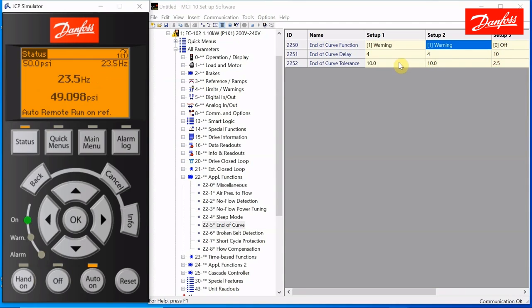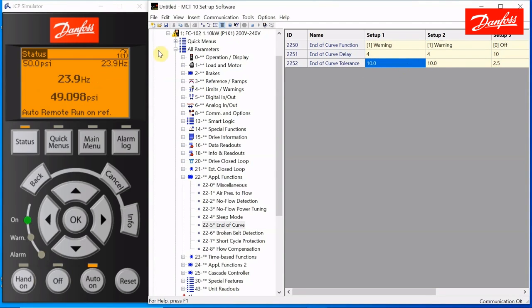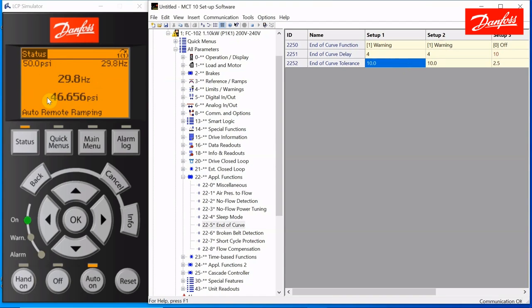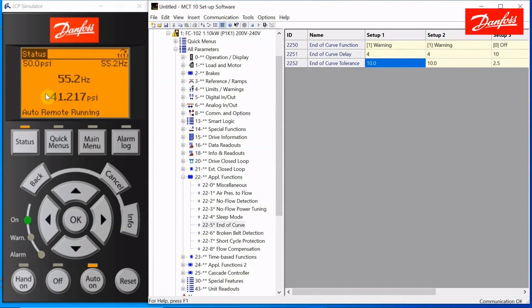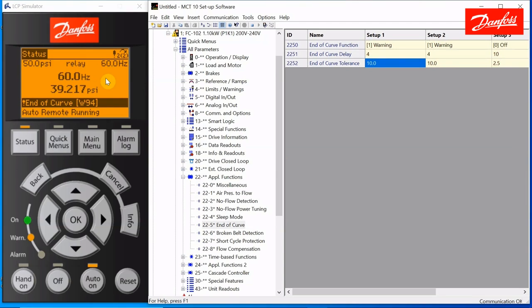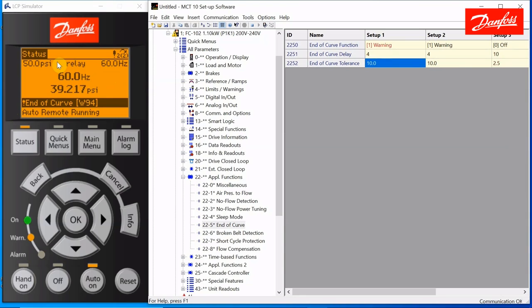With this set at 10%, that's 10 psi, if the pressure should drop to less than 40 psi while running at full speed, we should get our end of curve situation. So let's just drop the pressure down. We'll go to 41 and watch that speed wind up. It's trying to build that pressure back up, but it can't. It's running into a broken pipe. If this should drop lower than 40, then it's going to wait this four seconds before it shows end of curve warning. Still running at 60 hertz, but it's activated the relay. You could also activate a digital output, or serial comm can pick up on that, or you can use end of curve as an argument in the smart logic, but it'll keep on running.